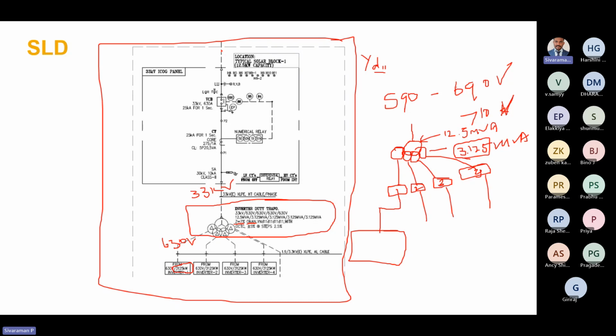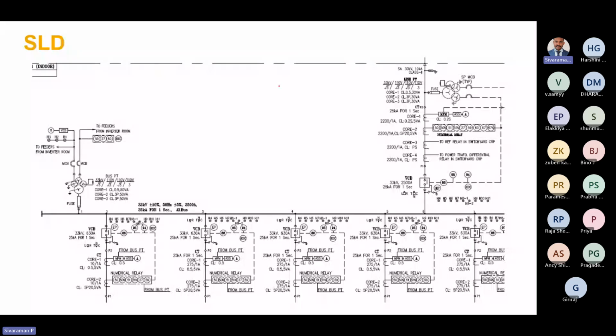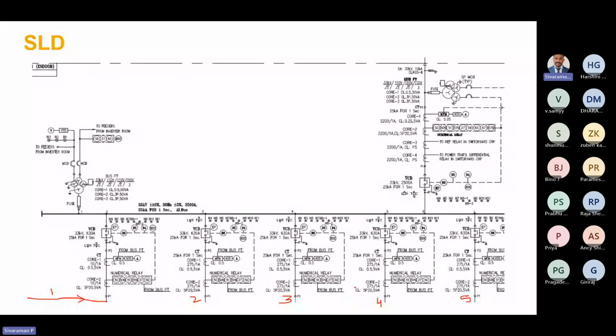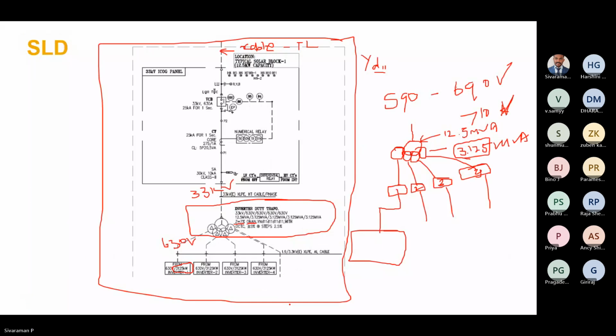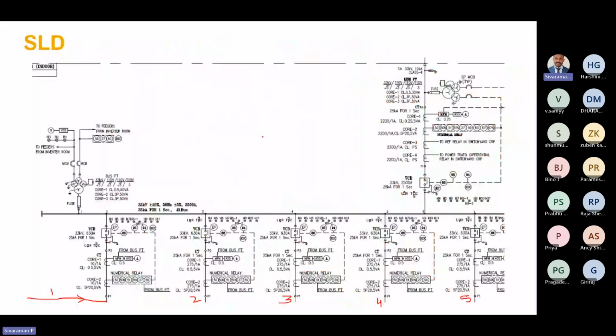Okay, so this outgoing will be mostly with cable or sometimes a transmission line as well. Okay, so this will go to the switchgear. So in this slide, what you are seeing is a 33 kV switchgear panel in the substation. It will have multiple incoming supplies from the solar PV area. This is 1, 2, 3, 4, 5. So this panel has 5 incoming supplies from the inverter room, and it has one output to the power transformer.